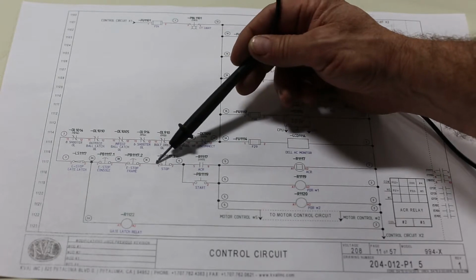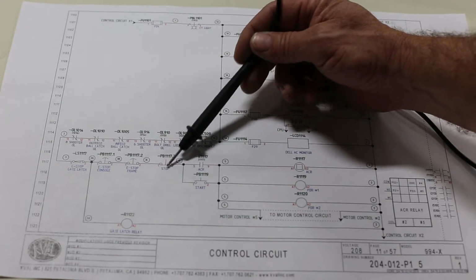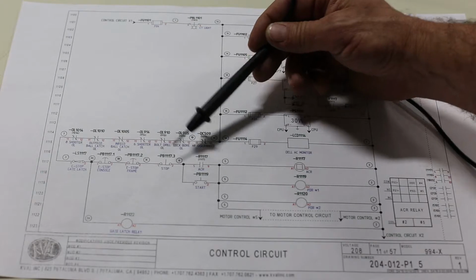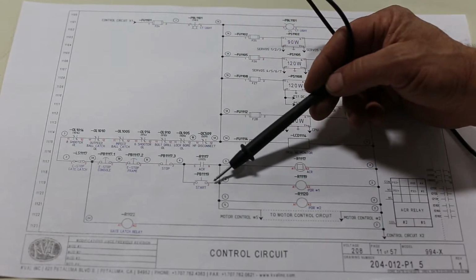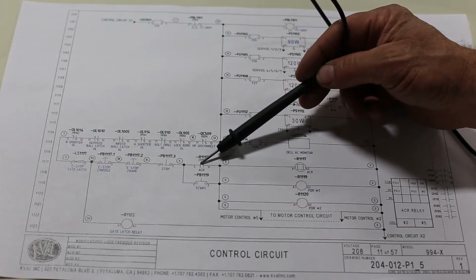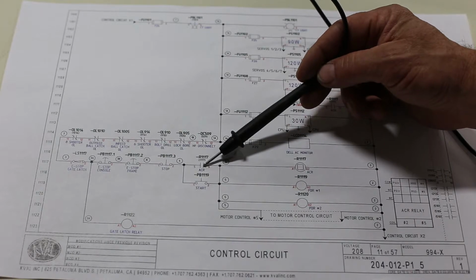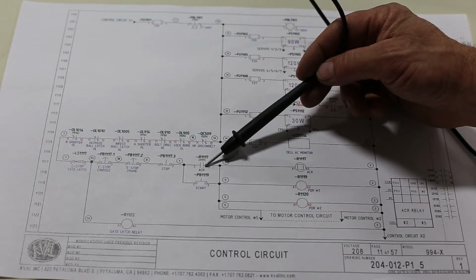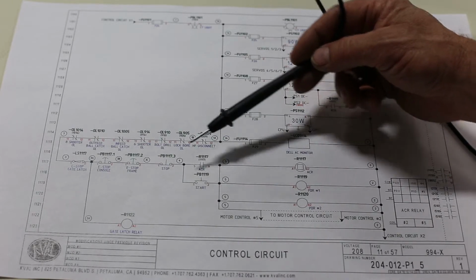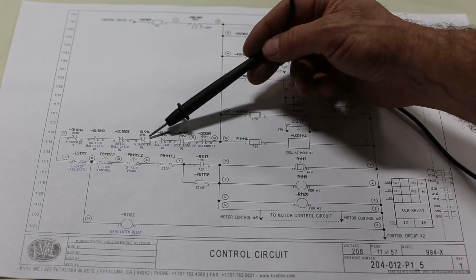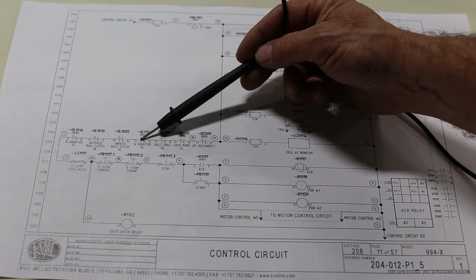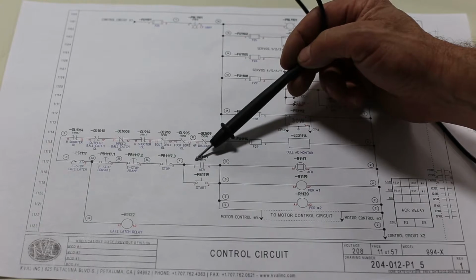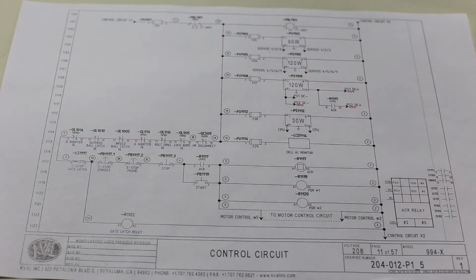Then we have our stop button. If that circuit is closed, we go to 4. And then we hit the start button down here. That latches the ACR circuit, which turns on the ACR, which holds it. Now, anytime any one of these buttons or E-stops or overloads are tripped, it's going to turn off this ACR circuit, and then you're going to have to go and do your troubleshooting.